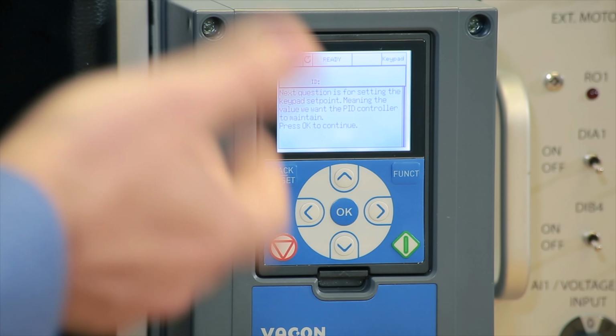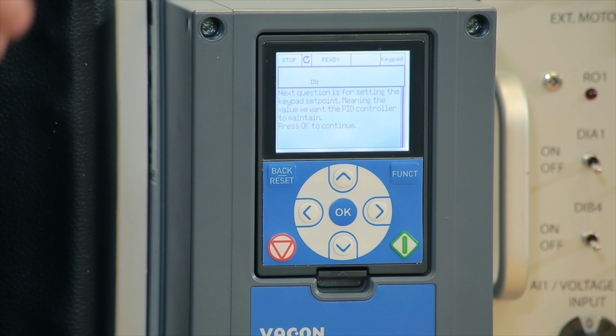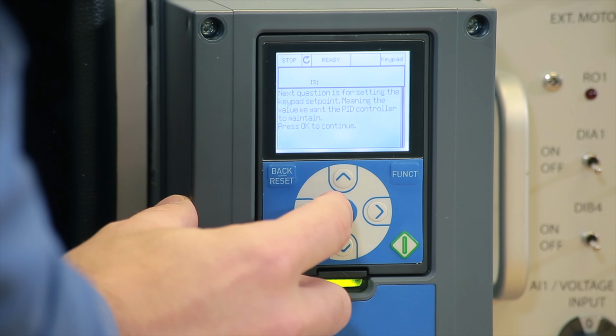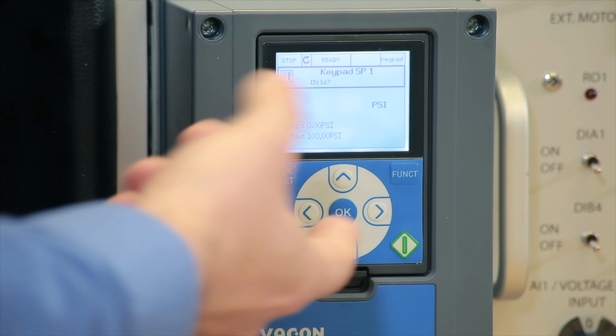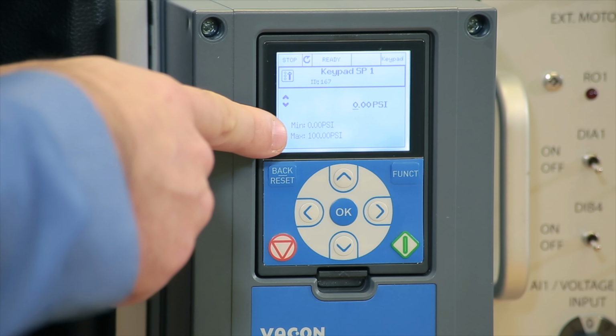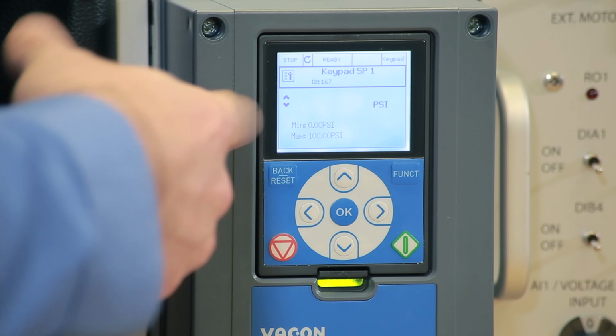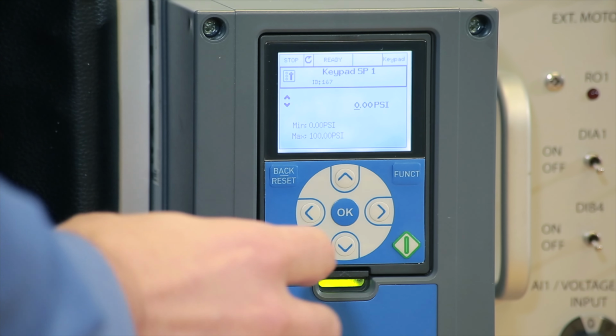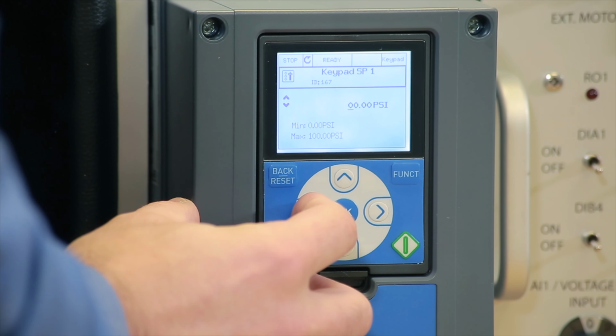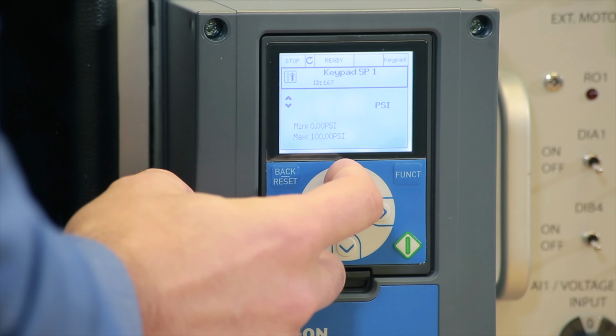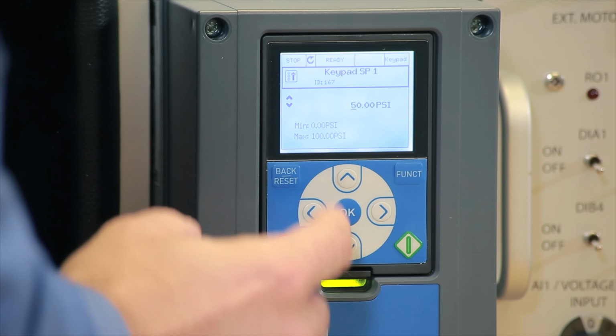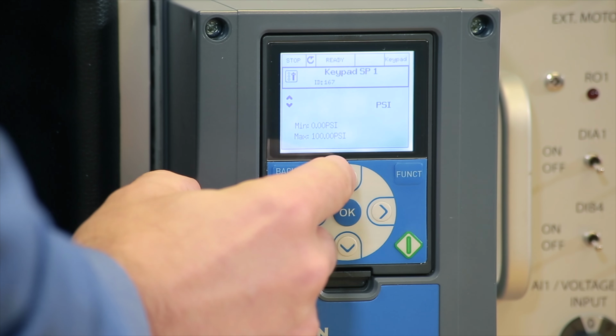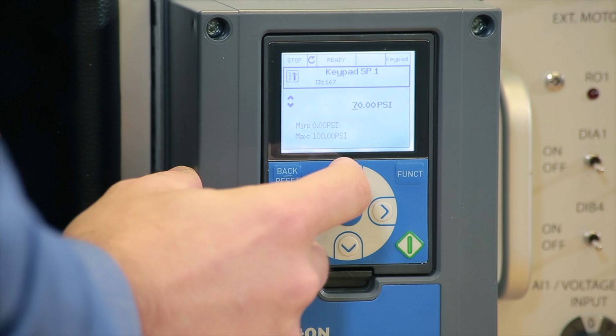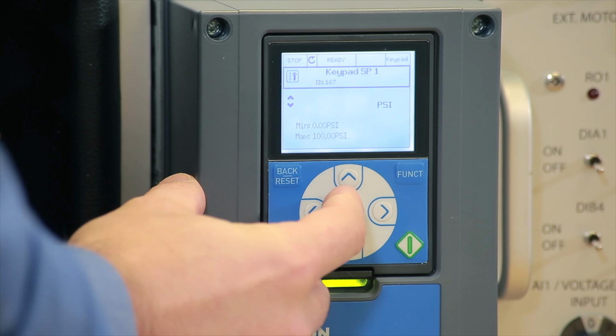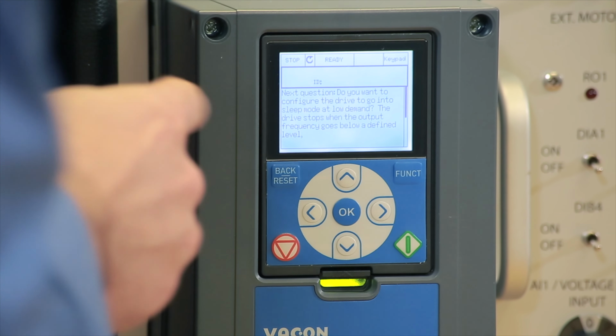So the next question is for setting the keypad set point. Basically it says, you've selected your keypad, now tell me what is the value of the PID that you need as a set point to be maintained. So it flashes 0, minimal is 0, maximum is 100, because this is what we programmed for a pressure transducer. So we could say we want the pressure set point to be 80 psi. So we're going to go left once and up 8 times. This is how we could get to 80. Okay, 80 psi. Next question.